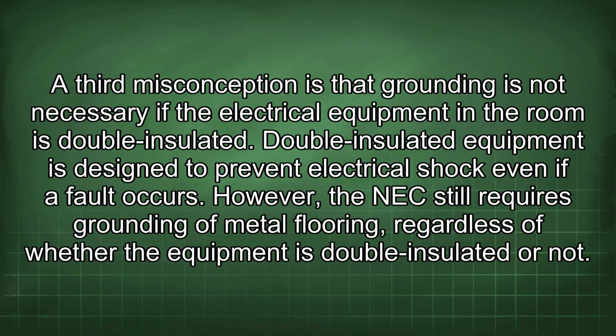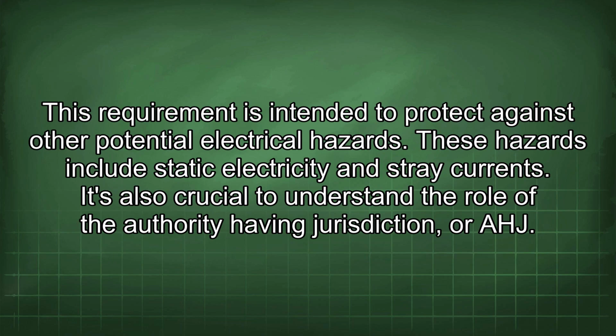A third misconception is that grounding is not necessary if the electrical equipment in the room is double insulated. Double insulated equipment is designed to prevent electrical shock even if a fault occurs. However, the NEC still requires grounding of metal flooring, regardless of whether the equipment is double insulated or not. This requirement is intended to protect against other potential electrical hazards. These hazards include static electricity and stray currents.